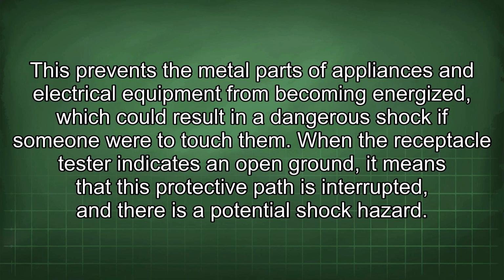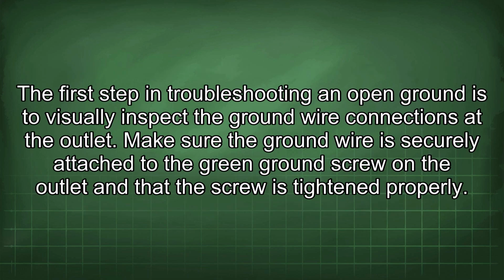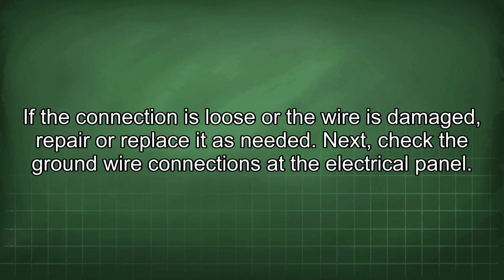When the receptacle tester indicates an open ground, it means that this protective path is interrupted, and there is a potential shock hazard. The first step in troubleshooting an open ground is to visually inspect the ground wire connections at the outlet. Make sure the ground wire is securely attached to the green ground screw in the outlet and that the screw is tightened properly. If the connection is loose or the wire is damaged, repair or replace it as needed.